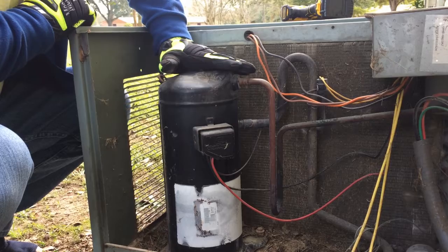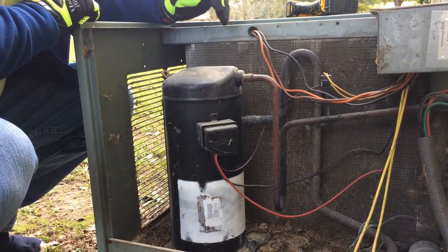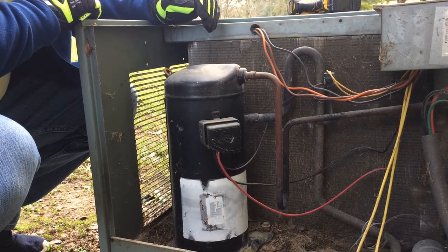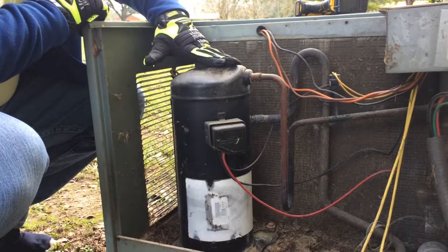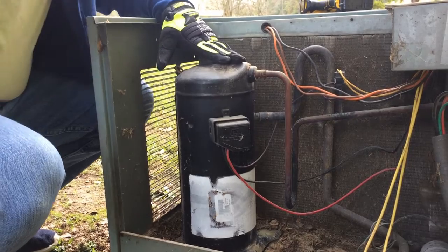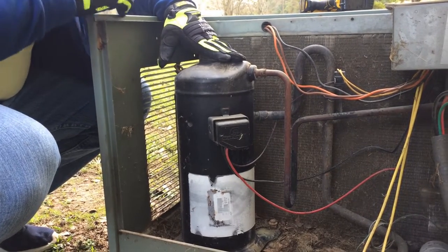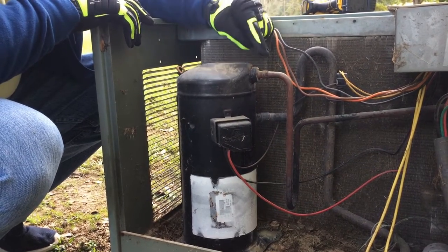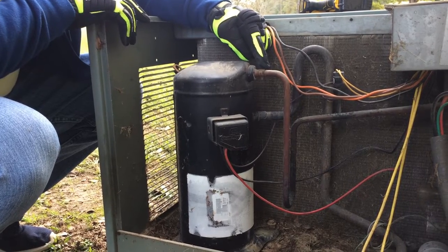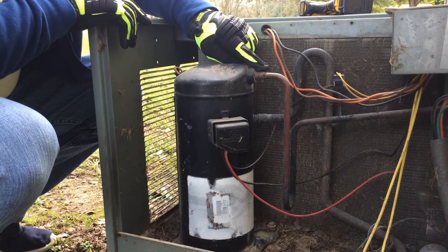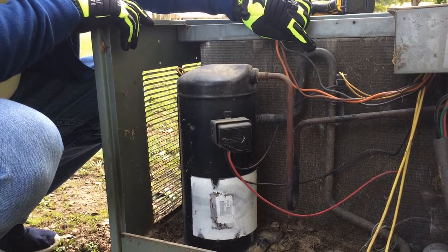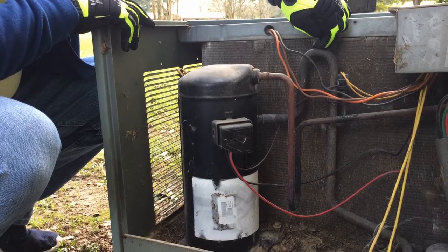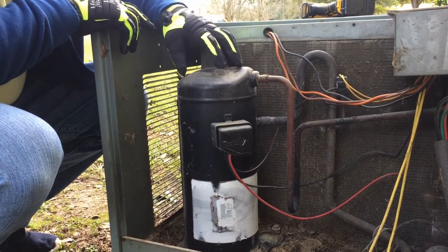And this is what a compressor looks like in its natural habitat. You can think of the compressor as the heart of your refrigeration system. In fact, it does the same function. What it does is it actually pumps the refrigerant through the refrigerant cycle. And it does this via copper tubing. You can see the smaller of the two is the discharge line. The refrigerant is actually leaving the compressor and going to the condensing unit, whereas the larger line, the compressor is sucking from the house into itself so that it can continue pumping.